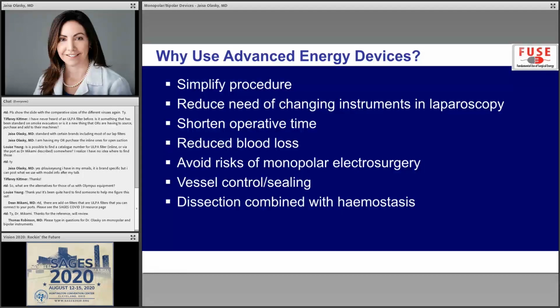A lot of these devices have vessel sealing capacity, but they also have the ability to cut the vessel. So you may be speeding up the procedure because you're not needing to put clips in and then cut, which is multiple instrument changes. Reduced blood loss has been shown with a lot of these advanced energy devices because they do provide a good seal, like we talked about with Dr. Mandani's slide. That coactive coagulation on cut mode is what these bipolar devices are achieving.